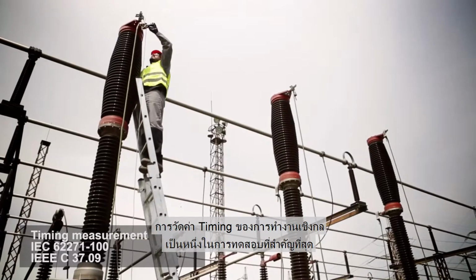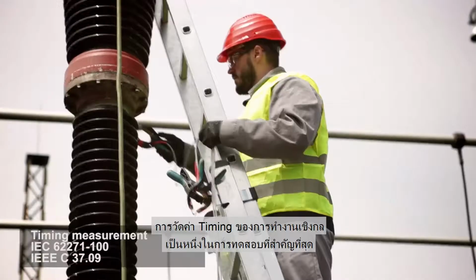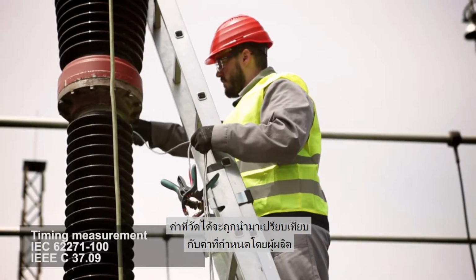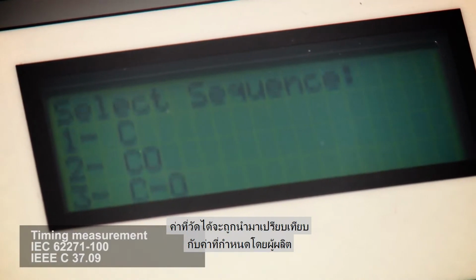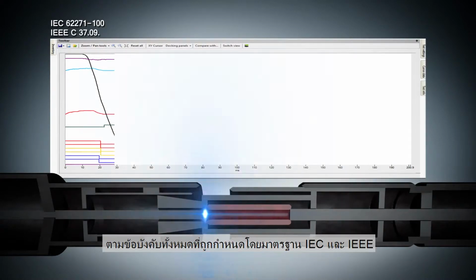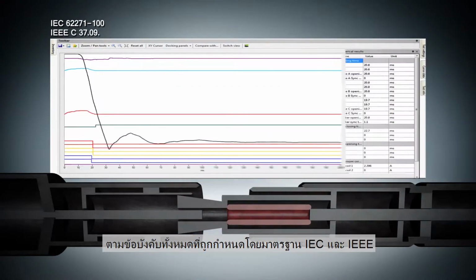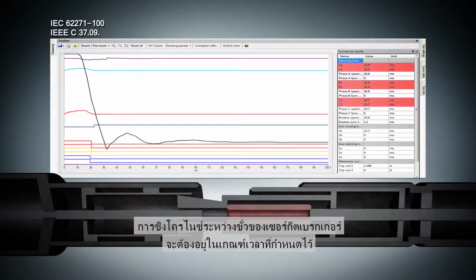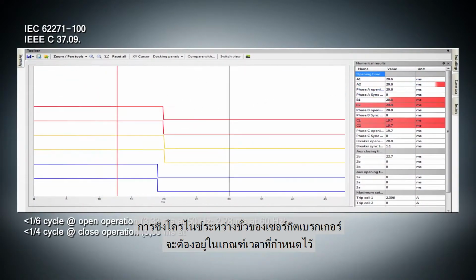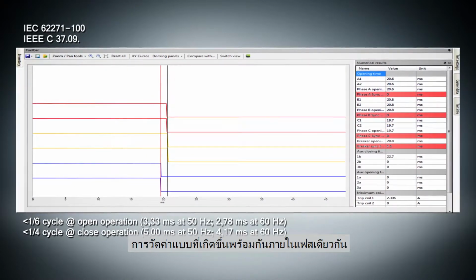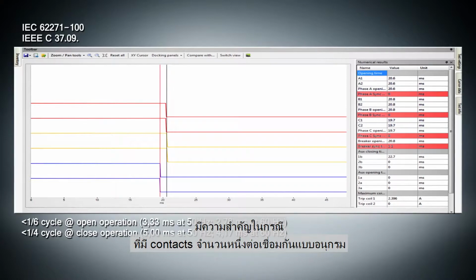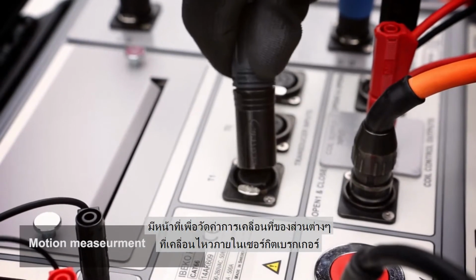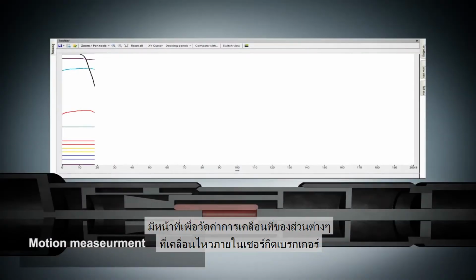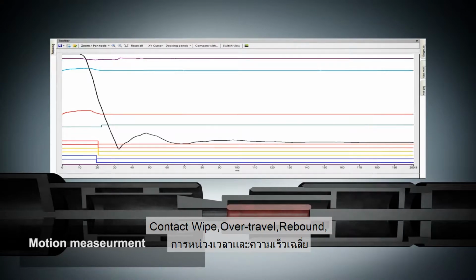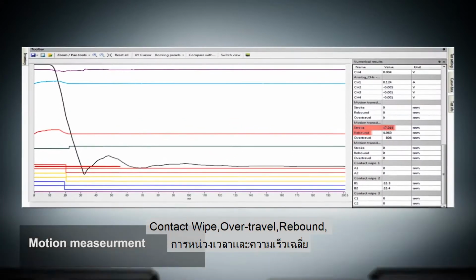The timing measurement of the mechanical operations is one of the most important tests to determine the real condition of the circuit breaker. Measured values are compared with limits specified by the manufacturer. Timing measurement tests fulfill all the requirements defined by IEC and IEEE standards. Synchronization between the circuit breaker poles has to be within specified limits. Simultaneous measurements within a single phase are important in situations where a number of contacts are connected in series. The free transducer channels are intended for measuring displacement of the circuit breaker moving parts, contact wipe, overtravel, rebound, damping time and average velocity.